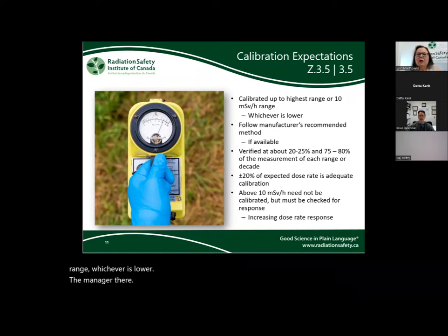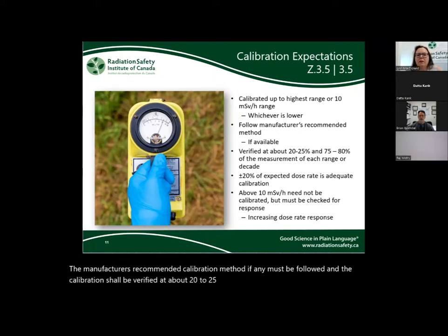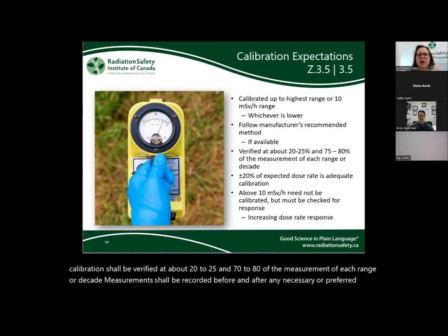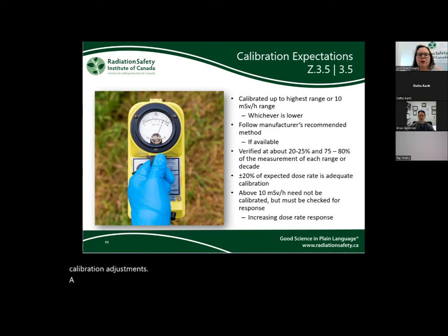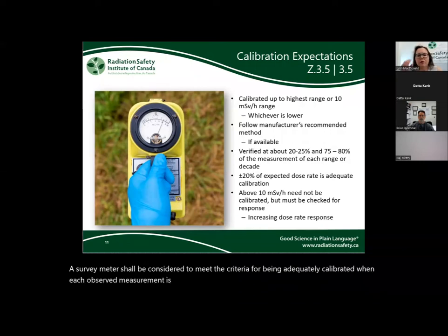The manufacturer's recommended calibration method, if any, must be followed, and the calibration shall be verified at about 20 to 25% and 75 to 80% of the measurement of each range or decade. Measurements shall be recorded before and after any necessary or preferred calibration adjustments. A survey meter shall be considered to meet the criteria for being adequately calibrated when each observed measurement is within plus or minus 20% of the expected dose rate.